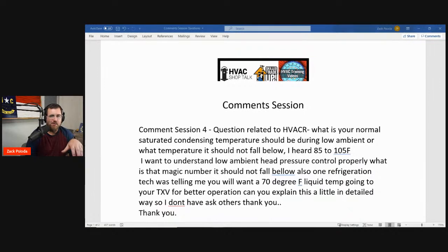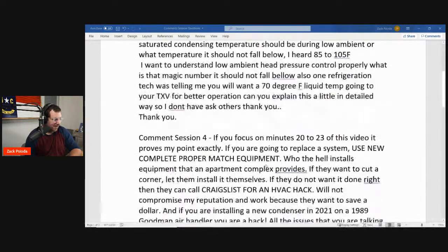You probably should ask people from other applications. There's a lot of refrigeration techs out there that might give you more information from a refrigeration standpoint. That would be my best advice, because I'm just going to go by where you can charge it or what they advise as far as charging. Because even at 70 degrees charging a TXV, 70 degrees is kind of low outside. I almost would want to come back and charge it again when it was 85, 90, 95 degrees. So I hope that helps a little bit. We're going to move on to the next one here.